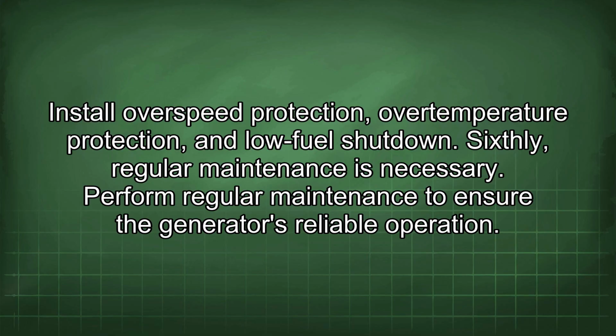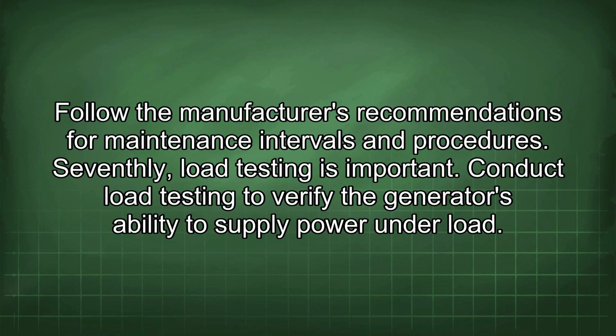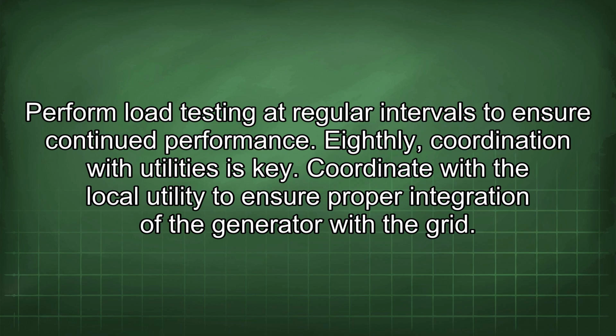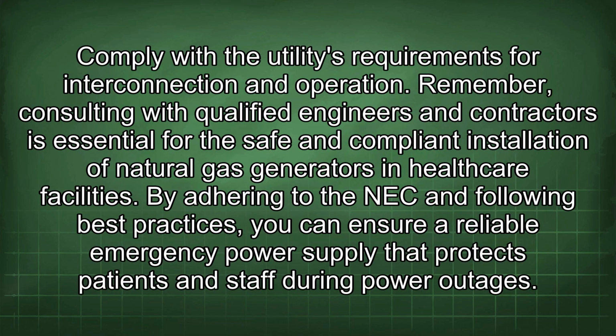Sixthly, regular maintenance is necessary. Perform regular maintenance to ensure the generator's reliable operation. Follow the manufacturer's recommendations for maintenance intervals and procedures. Seventhly, load testing is important. Conduct load testing to verify the generator's ability to supply power under load. Perform load testing at regular intervals to ensure continued performance. Eighthly, coordination with utilities is key. Coordinate with the local utility to ensure proper integration of the generator with the grid. Comply with the utility's requirements for interconnection and operation.